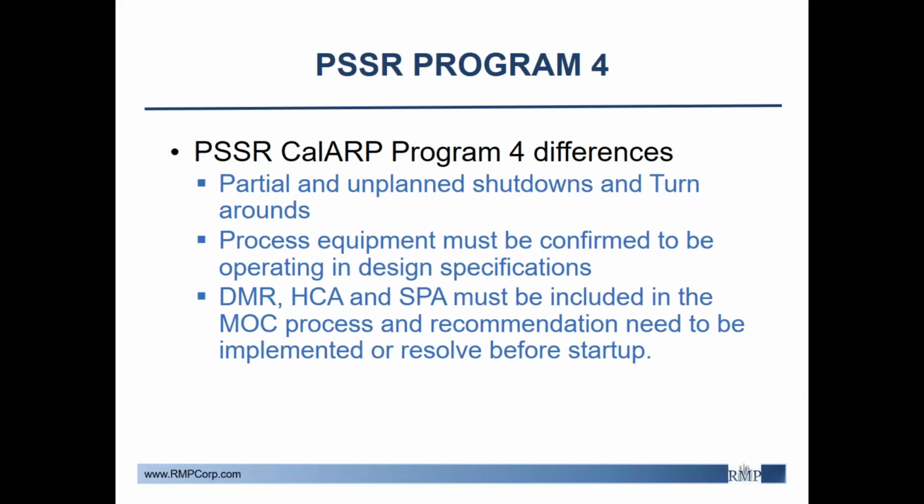So let's touch on the program 4 differences. And this is, again, why it's important to think of PSSR as its own element. You don't just think of it as MOC, right? Especially for program 4 now, you're required to do them for partial and unplanned shutdowns and turnarounds. So a lot of times you don't actually make any changes when you're doing these things, right? When you have an unplanned shutdown, sometimes it's just a spurious trip. You figure out a way to start back up.